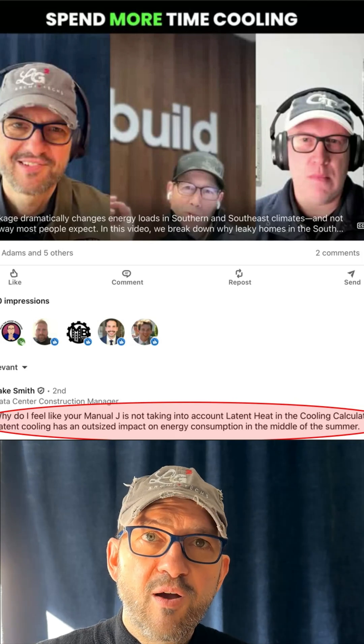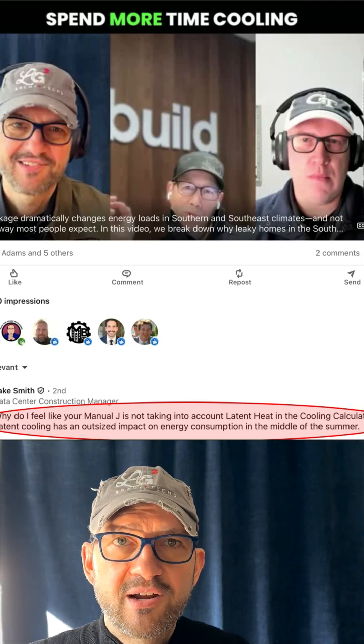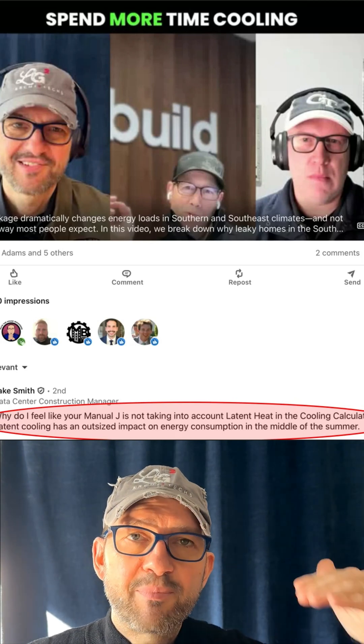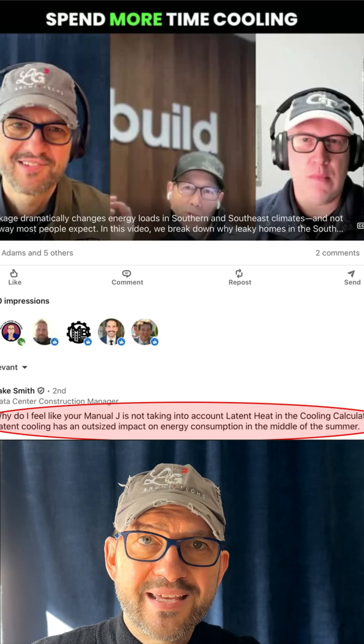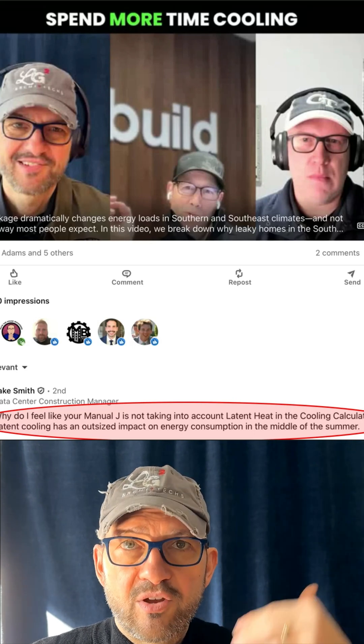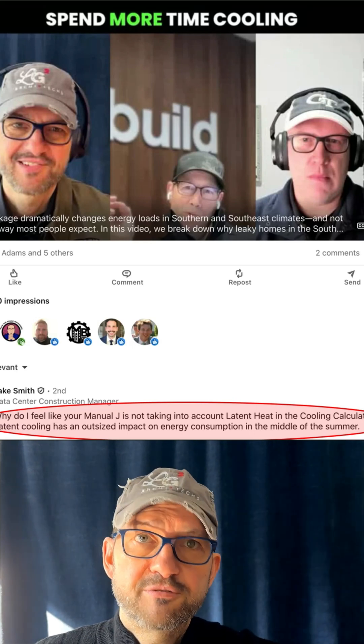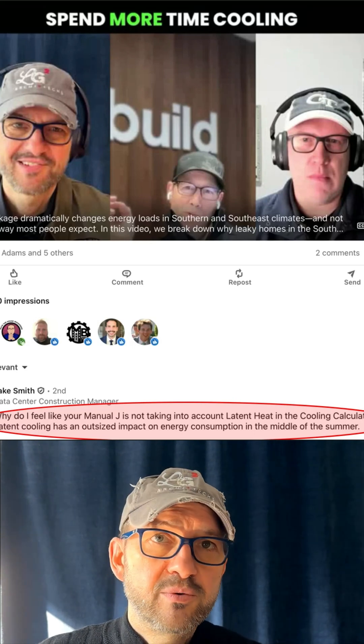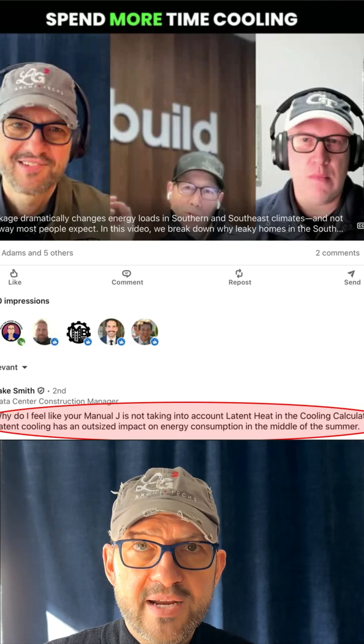We did a video about what happens when we change the air leakage, what happens to the loads, especially the heating. And we saw that when we go from zero to 5 ACH50, which is code, we doubled our heating.